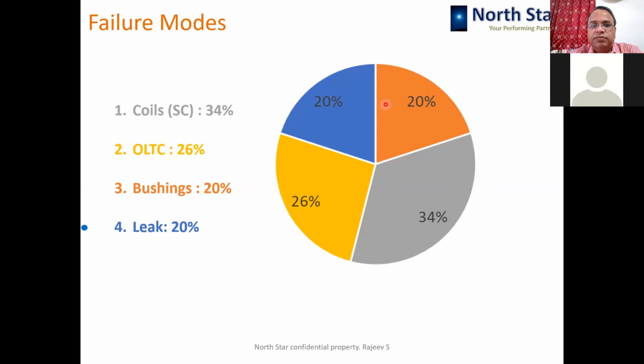Especially if you look at the small distribution transformers, pole mounted transformers, many times they are without a conservator, and sometimes the conservator is also there, but because of leakage the oil keeps on leaking, and the oil level drops below the HV leads which are going to the bushing, and it is not rightly maintained, so wet air goes inside, and this deadly combination of moisture, oxygen, and low oil level causes sparking in the transformer, and as a result it catches fire. The fire starts, the pressure builds up, and it explodes like a bomb.